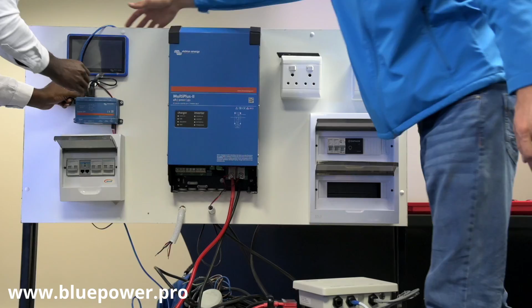Must you plug that right in behind there? Yeah, you must plug it in. So for VE CAN, it's a requirement to have the terminations on the beginning of the communication line and the end of the communication line.